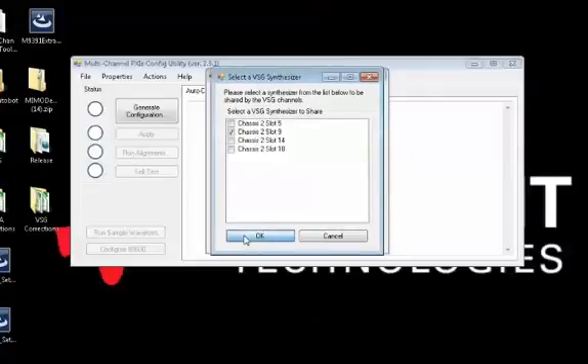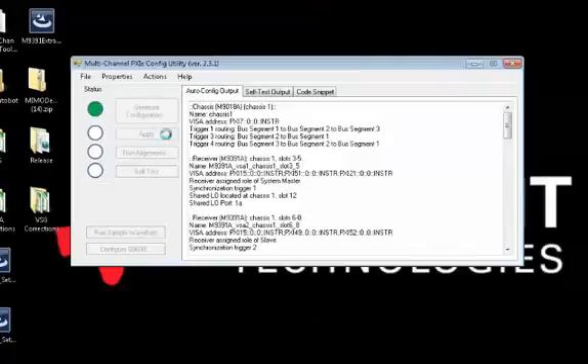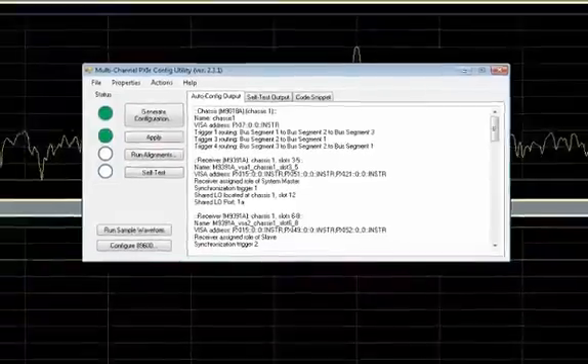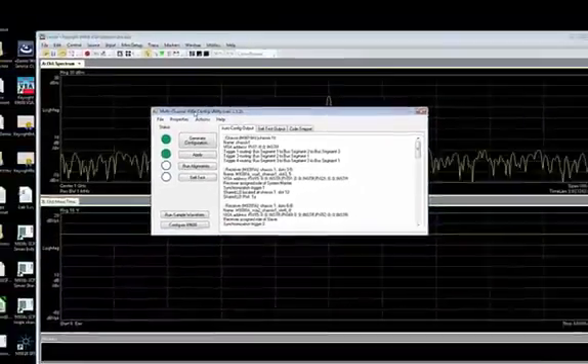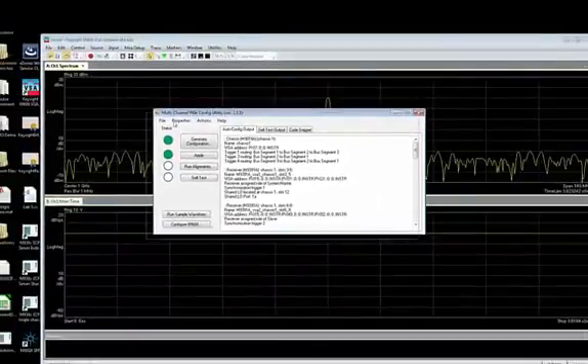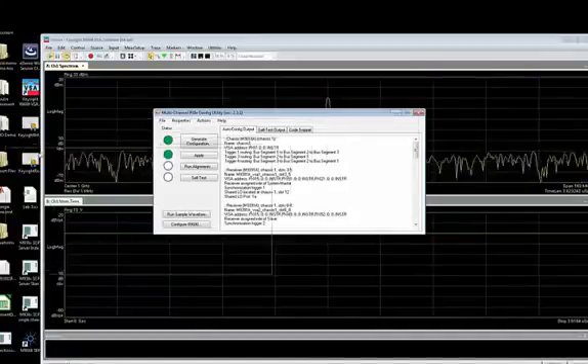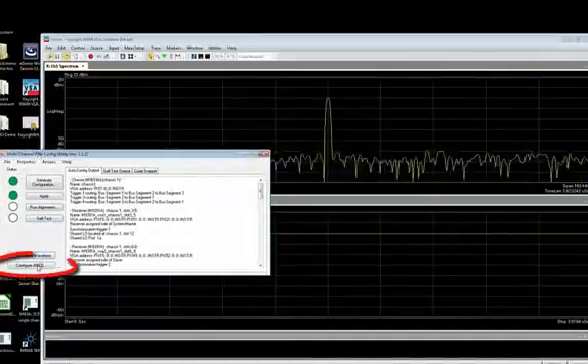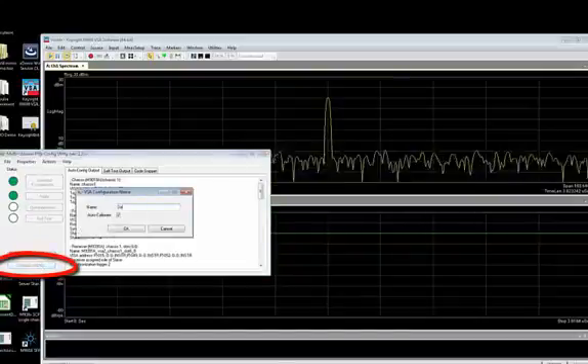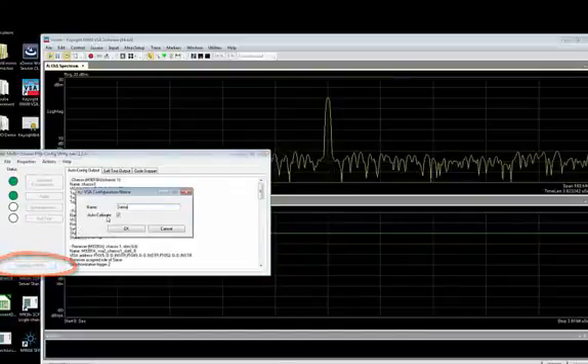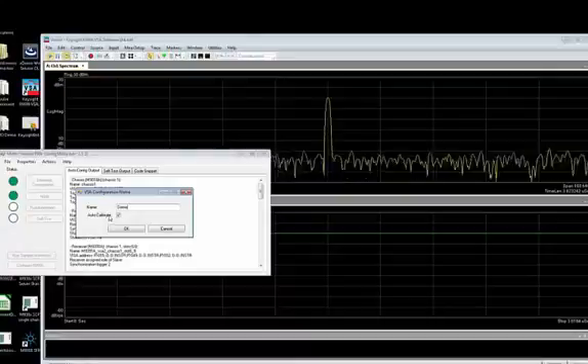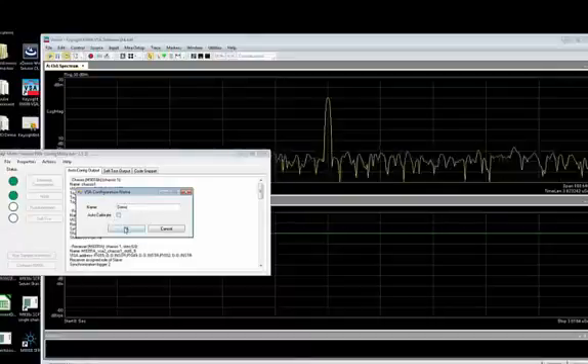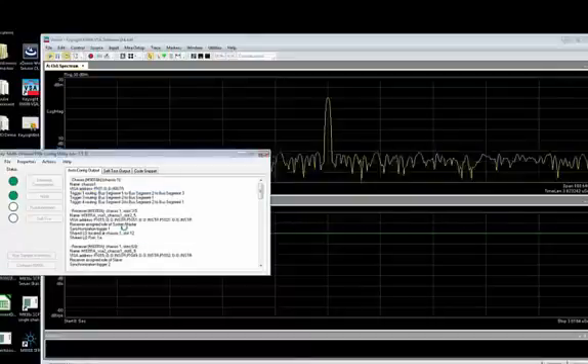Once we have identified the configuration, we select apply and the configuration utility configures the instruments for multi-channel operation and routes the PXI backplane triggers to support the phase coherent synchronization between multiple PXI instruments. Now we can select the config 89600 button and provide a VSA software configuration name. The configuration utility will then set up the VSAs for four-channel analysis.